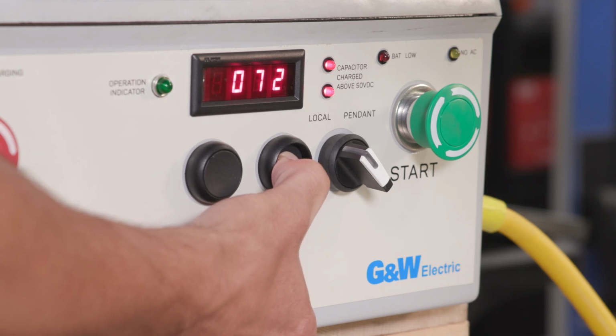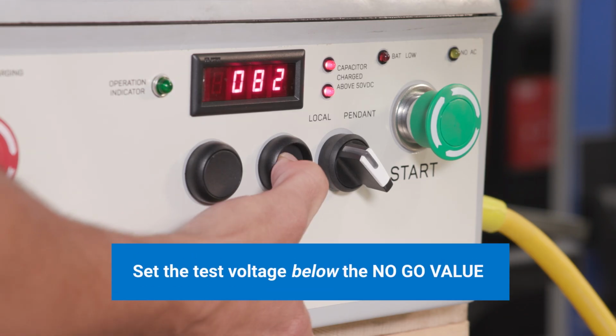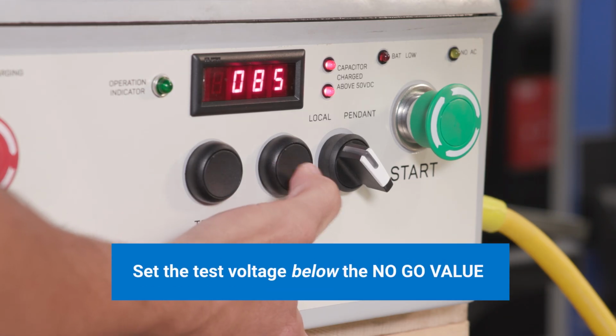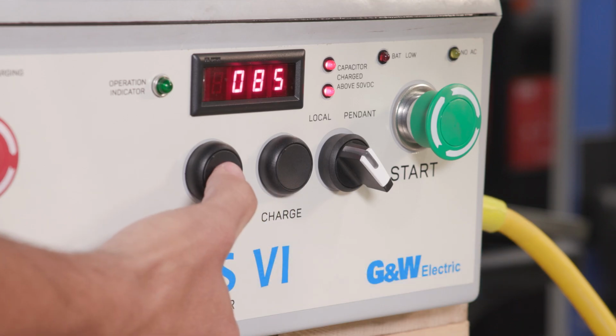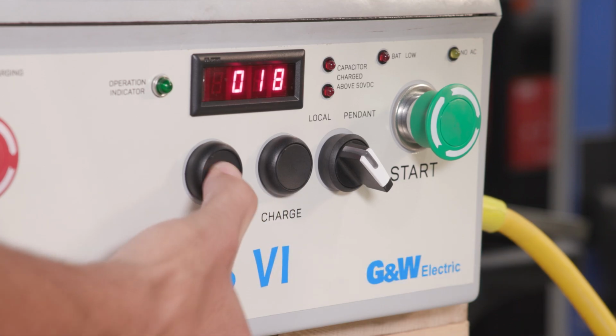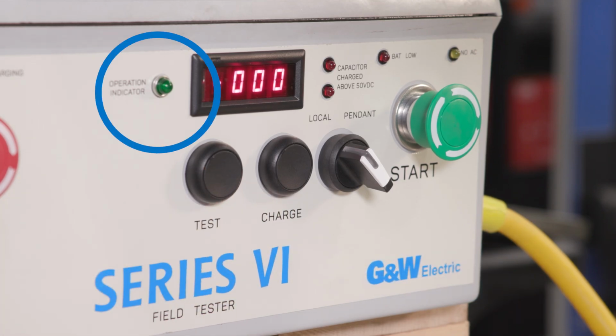Now set the test voltage below the no-go value located on the black nameplate. Press the test button and verify that the SFL does not fire. The field tester green LED will not illuminate.